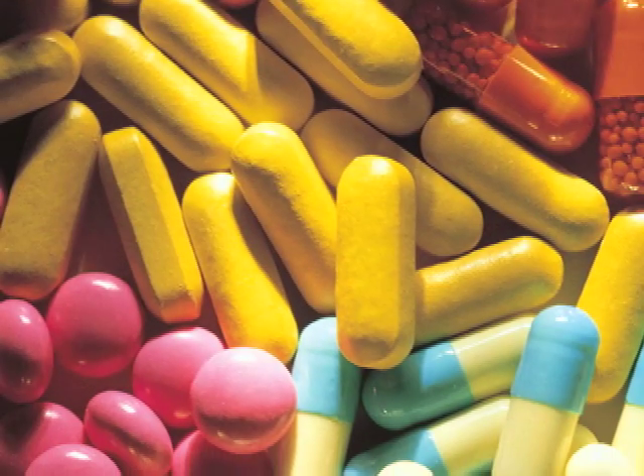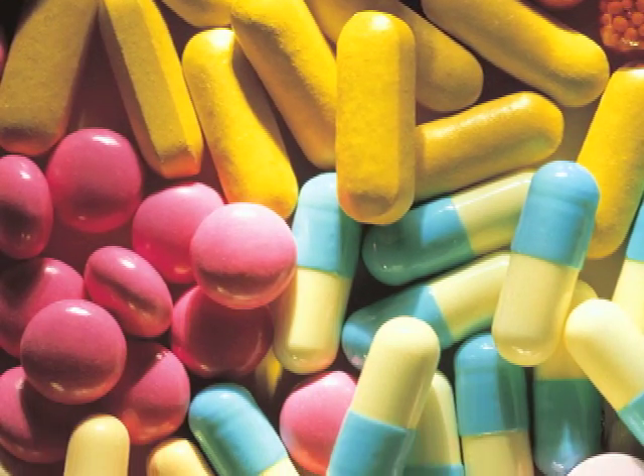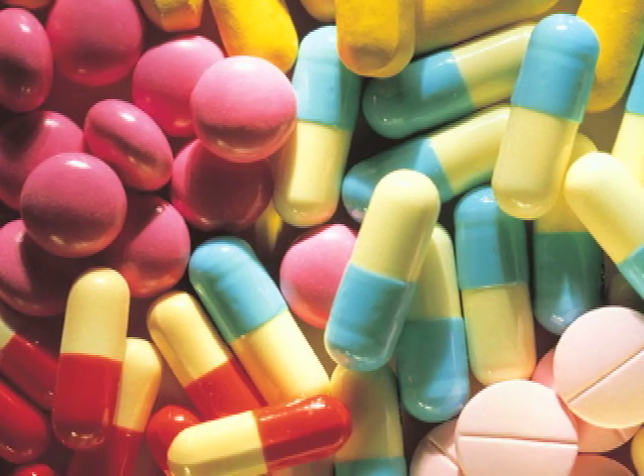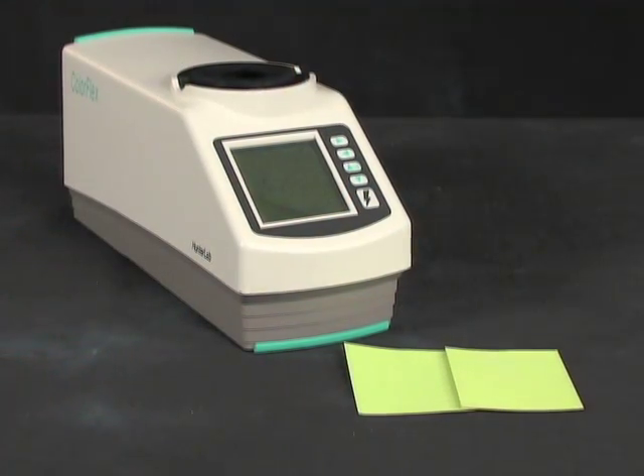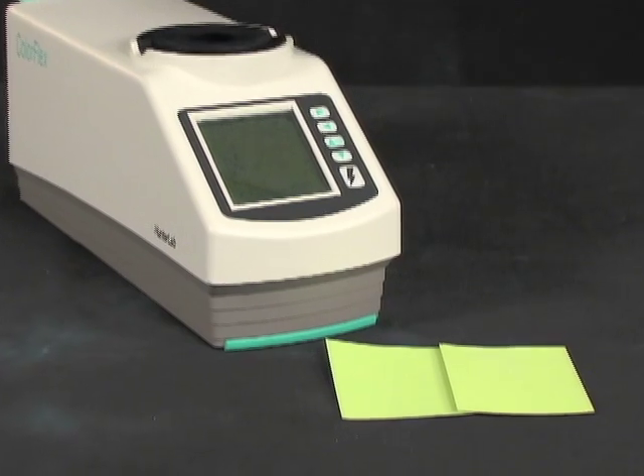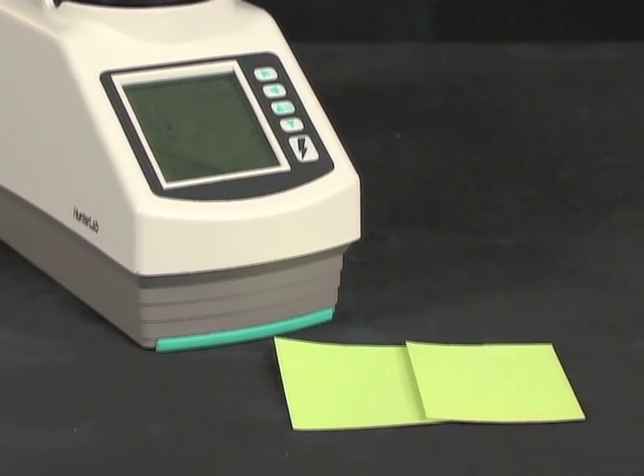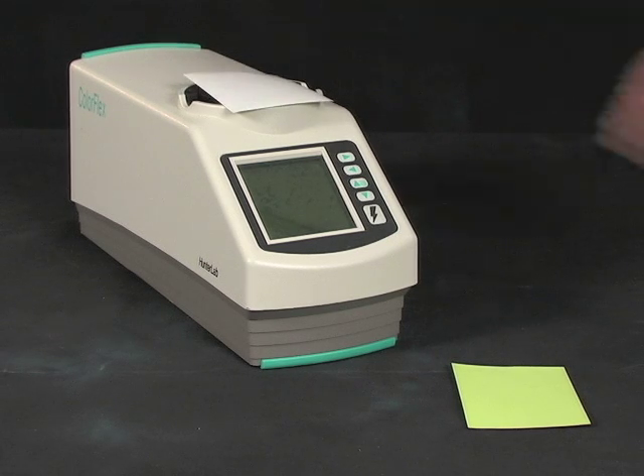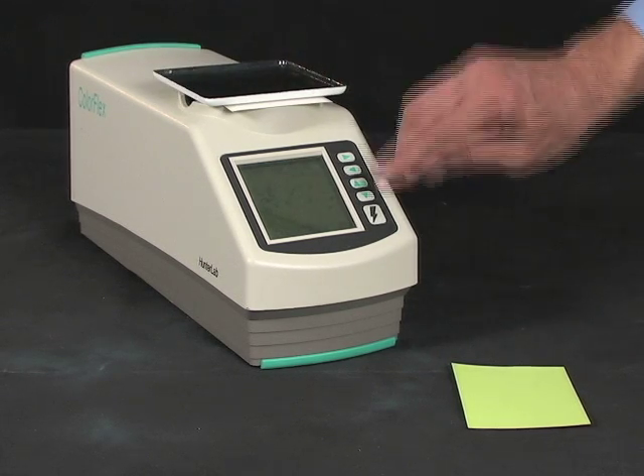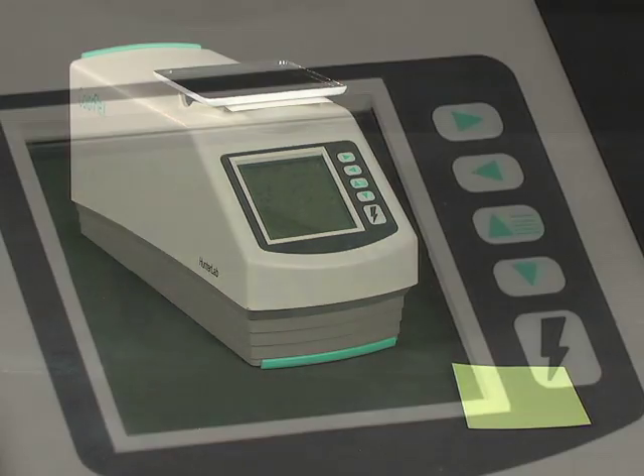It is frequently important to know the difference between two samples or between a sample and a target standard. We will use the HunterLab ColorFlex to measure the difference between a pair of green samples. The first sample is placed on the instrument measurement port and a button is pressed to take a reading. The values displayed represent that specific color of green.